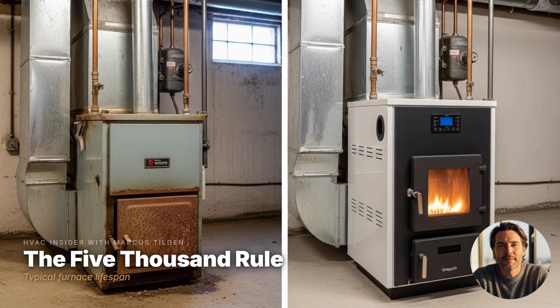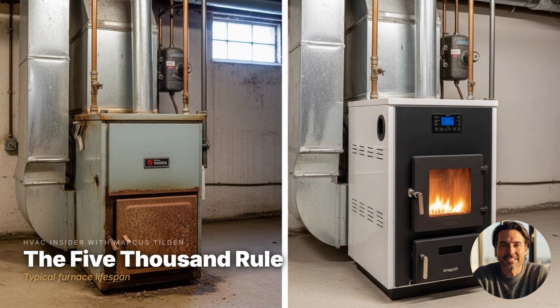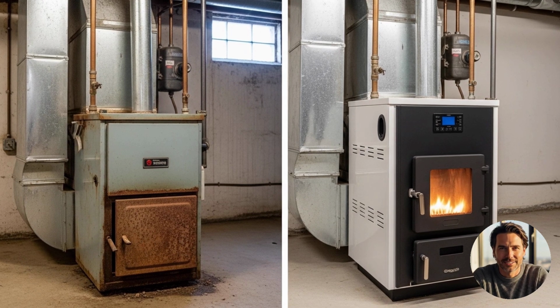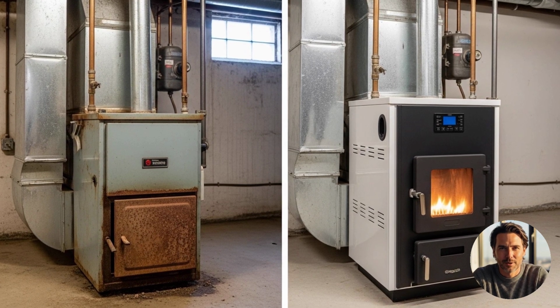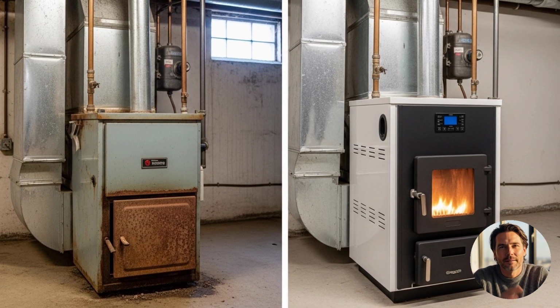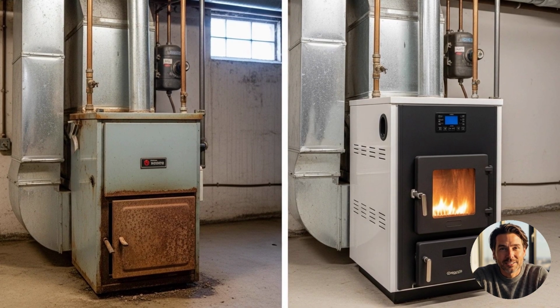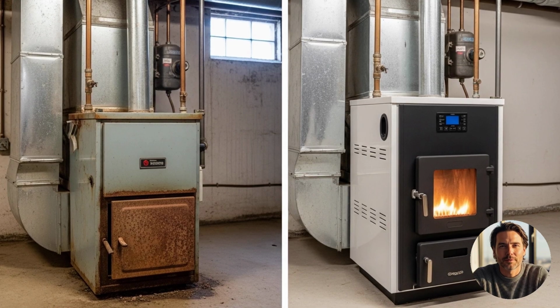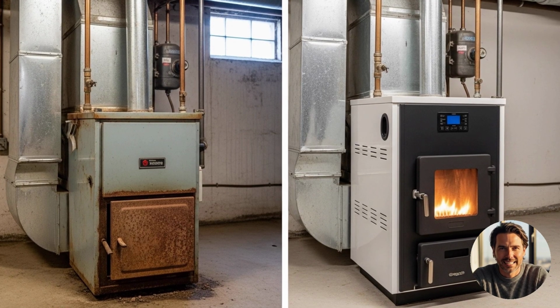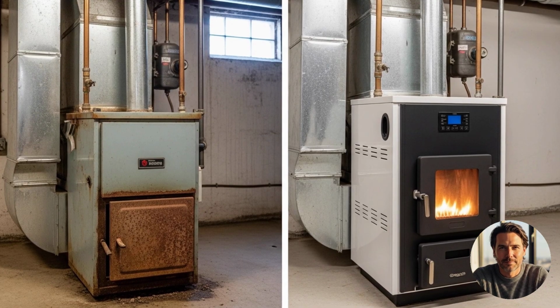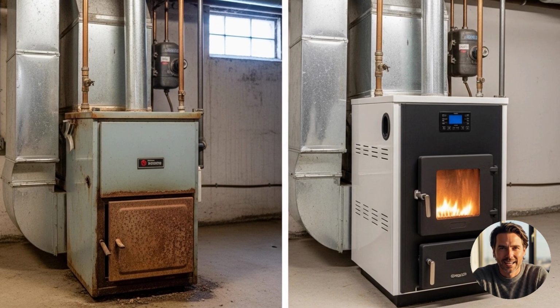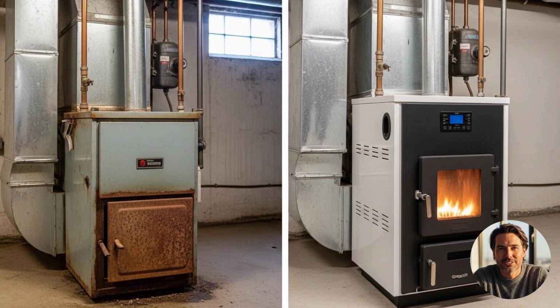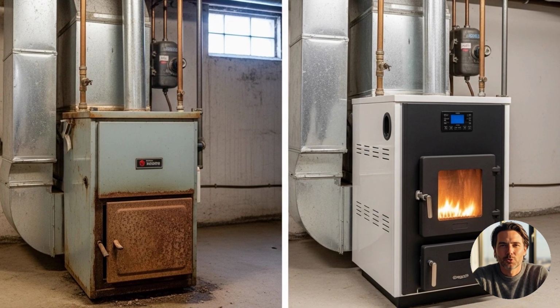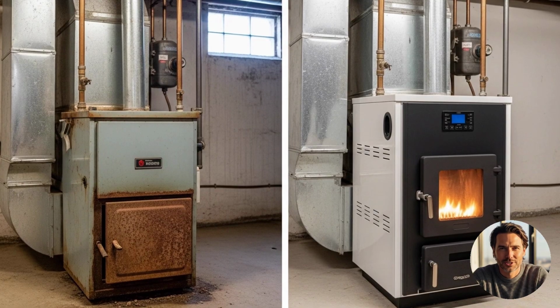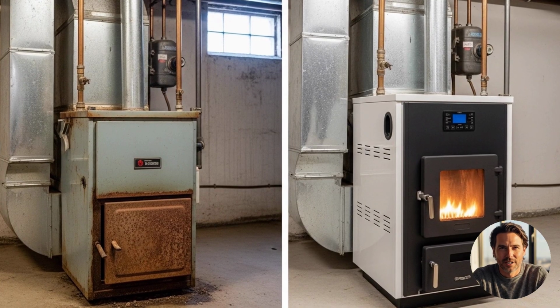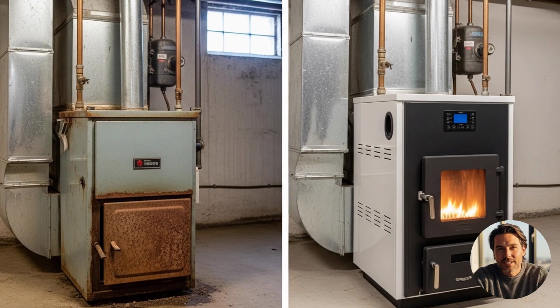Start with age. Furnaces commonly last 15 to 20 years, and central air conditioners and heat pumps commonly last 10 to 15 years. Then use a quick gut check some techs call the 5,000 rule: multiply the repair cost by the age of the unit in years. If that number climbs past about 5,000, replacement starts to make real sense. A $300 repair on a 6-year-old furnace is easy. The same repair on an 18-year-old unit is a different conversation.